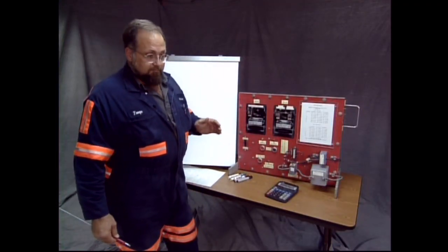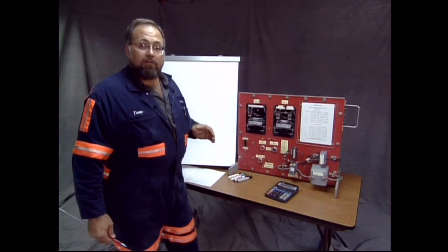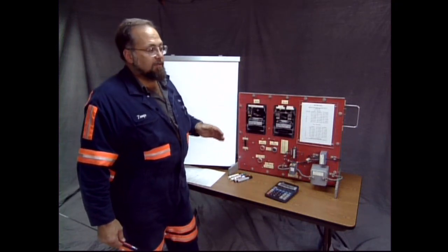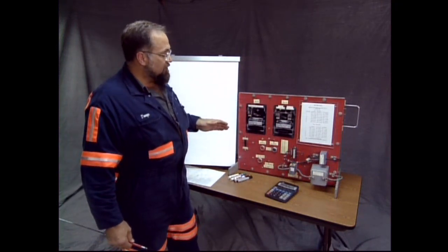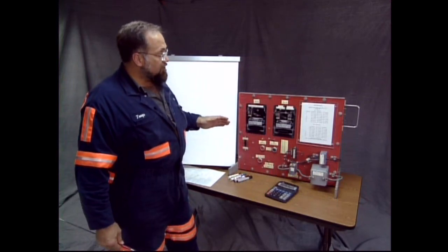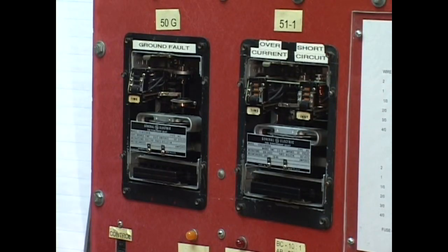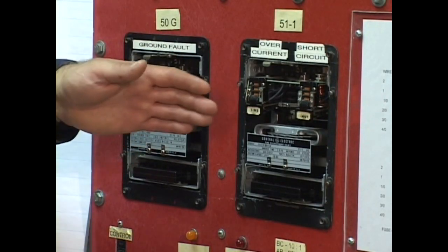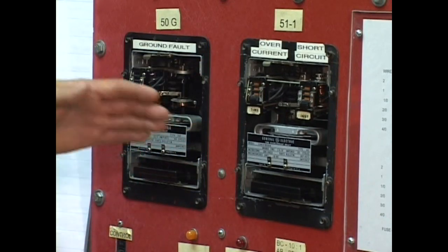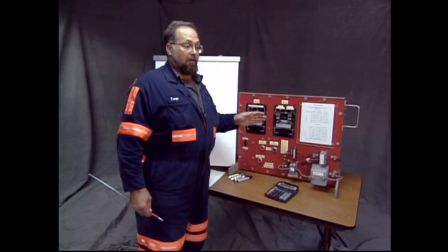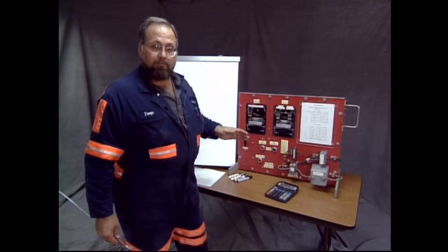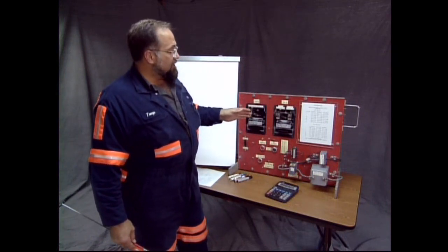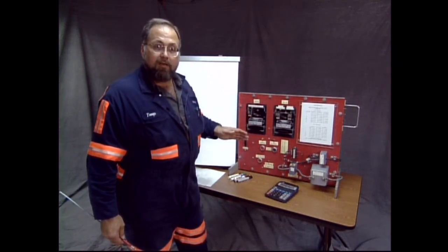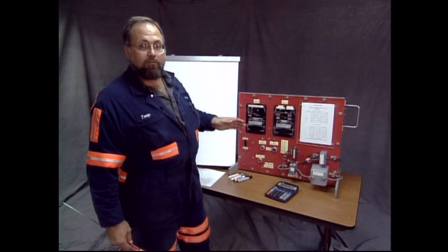Now, manually operate 2 auxiliary devices. Make a visual examination of the breaker and all its components, looking for any broken or missing parts. Even something as insignificant as an insect nest could block the operation of this relay. I once had a problem where a spider had gained access into a relay and stopped the contact. You're going to be looking for those things.